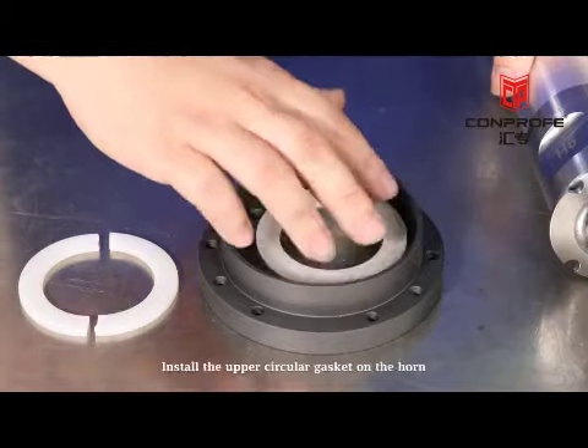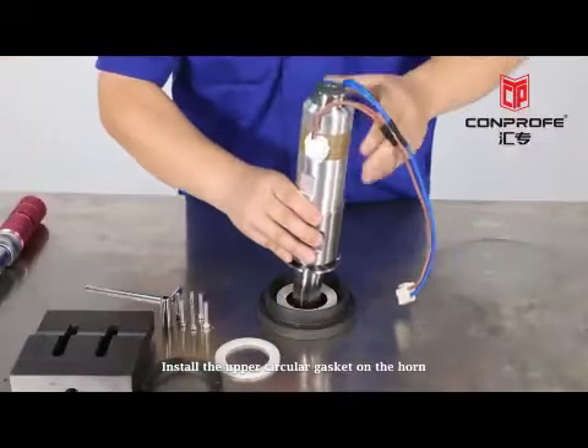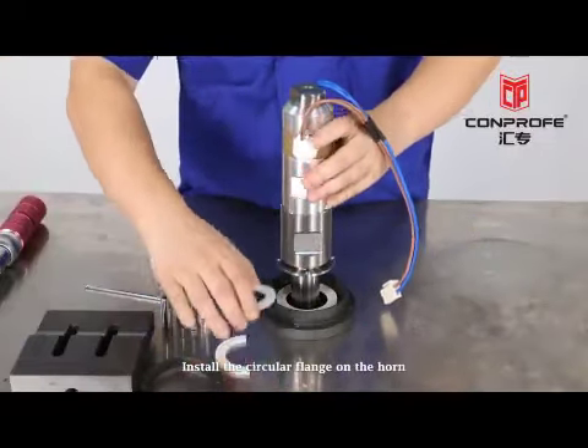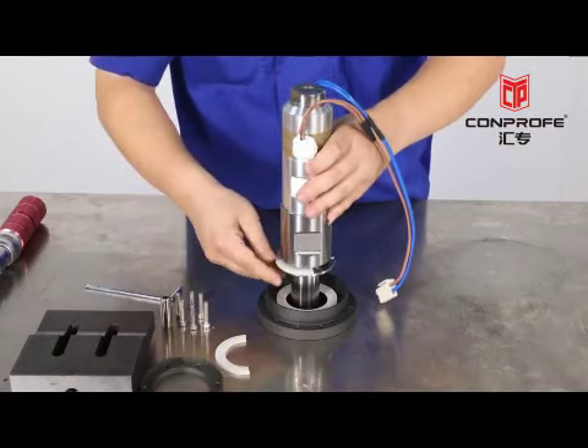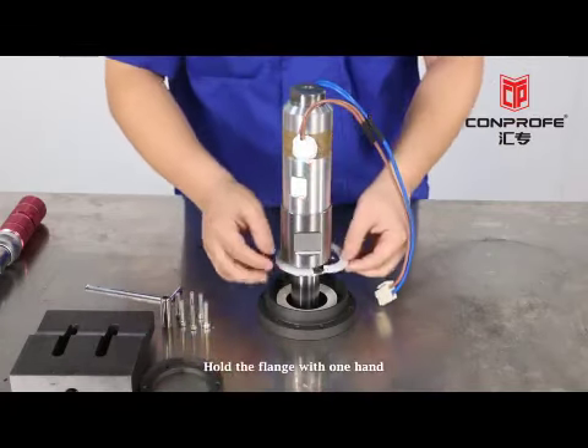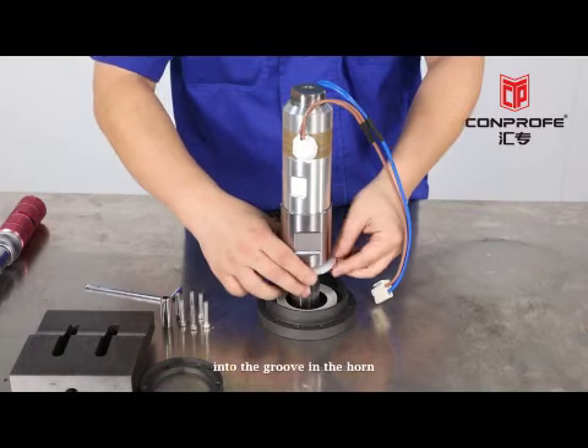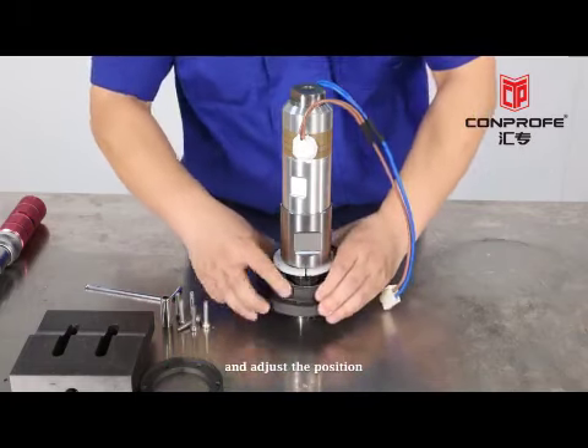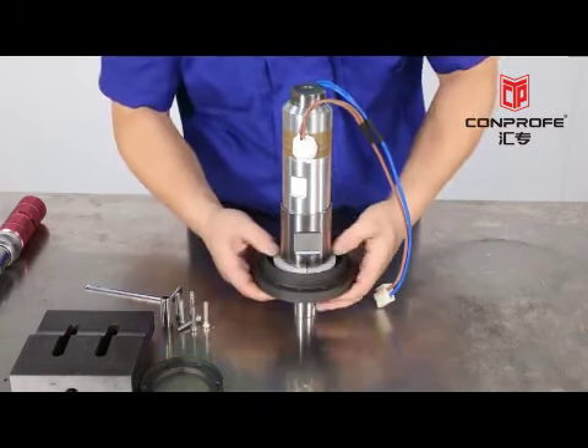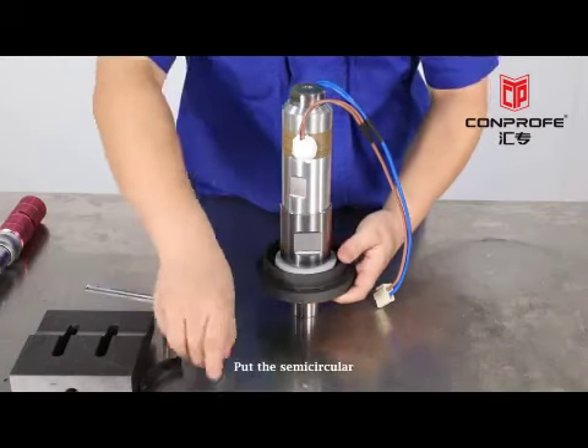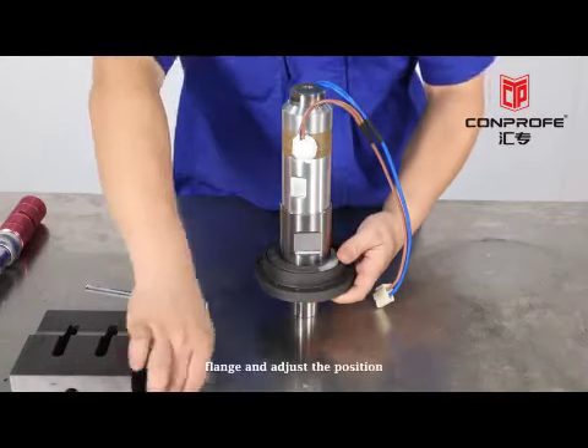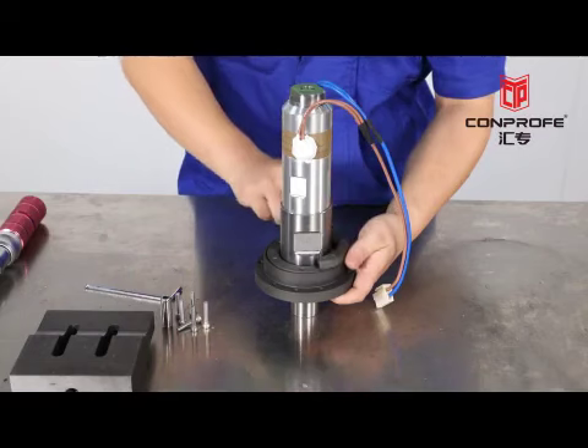Precautions for transducer installation. Install the upper circular gasket on the horn. Install the circular flange on the horn. Hold the flange with one hand, put two semicircular gaskets into the groove in the horn and adjust the position. Put the semicircular steel press block in the flange and adjust the position.